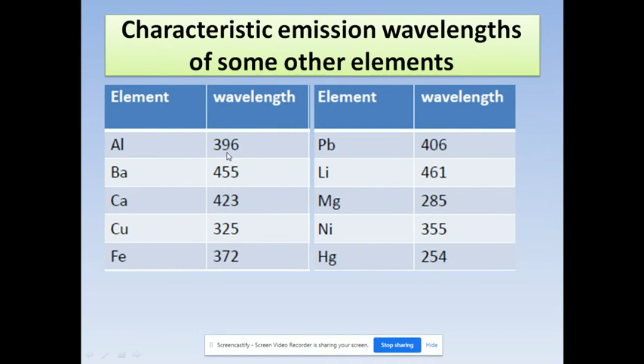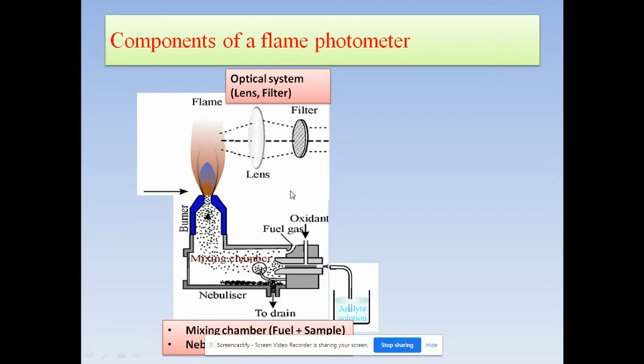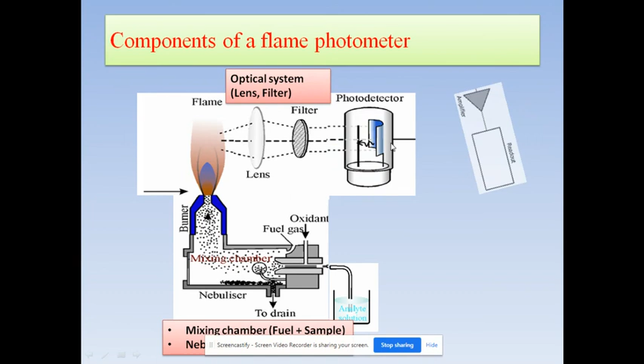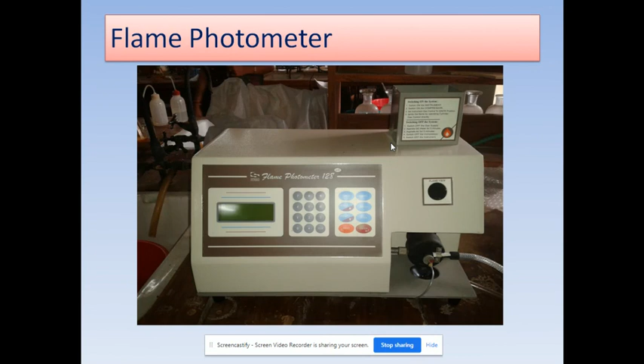Components of the flame photometer: here it is the analyte, and it is connected to a mixing chamber. Fuel gas is supplied, and it is connected to the burner. The atomizer is linked here, and the atomized sample is spread over the flame. Thereafter, excitation and de-excitation will take place, and certain wavelengths will be emitted. This emitted radiation is made to pass through a lens, and then through a particular filter, depending upon the type of analysis. Suppose I am going to analyze sodium, so I have to set this filter at the sodium wavelength. So the particular sodium wavelength is passed and the remaining are stopped. This is the photo detector, which is connected to the amplifier, and the reading will be obtained. This is the particular flame photometer usually used in the labs.